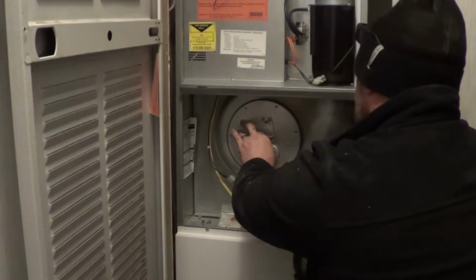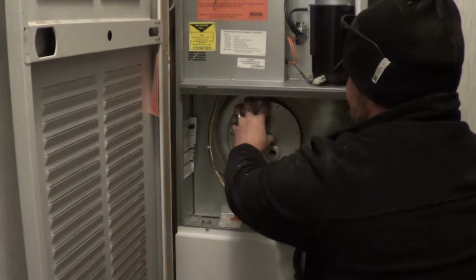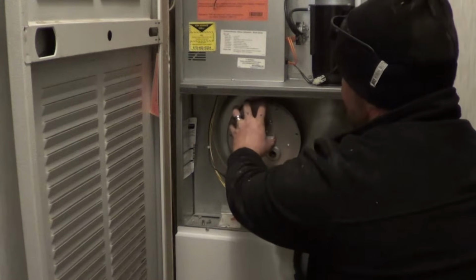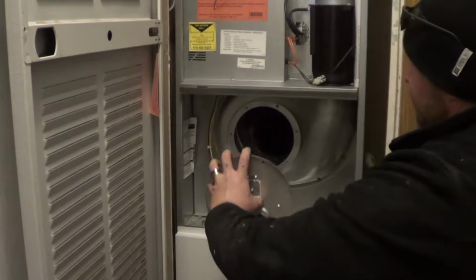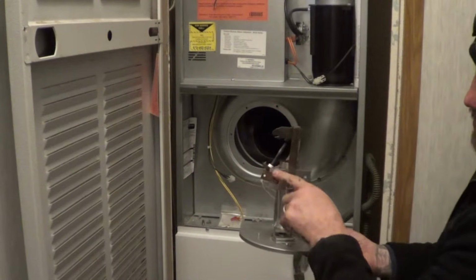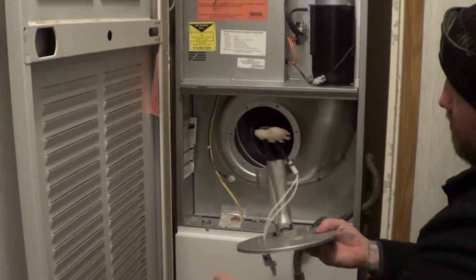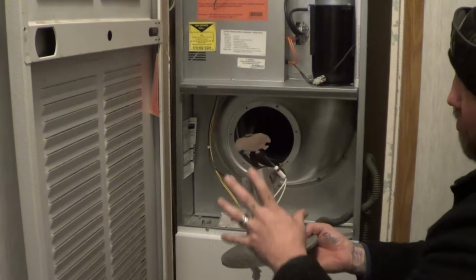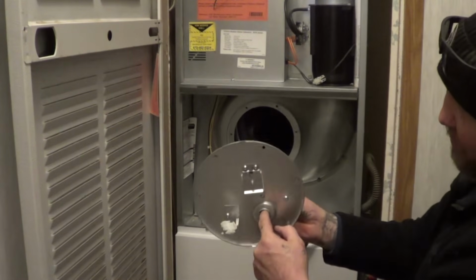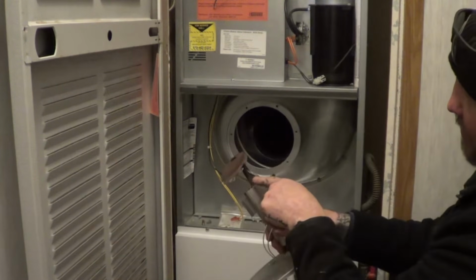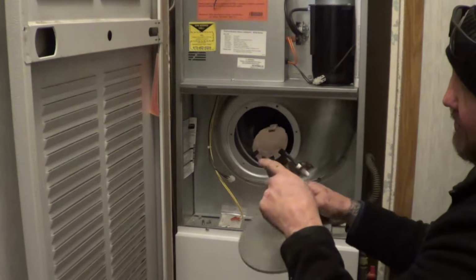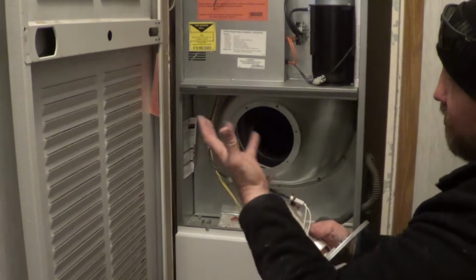So on this Intertherm furnace, we're going to lift the back end up, let the top fall a little bit, and then pull it straight out. Because we can see on here, here's the igniter. So here's the whole burner assembly. They call this the burner assembly. Of course, gas comes in here, comes out here, hits the igniter, ignites, and then hits this here, the spreader plate, and that's where you get your flame.